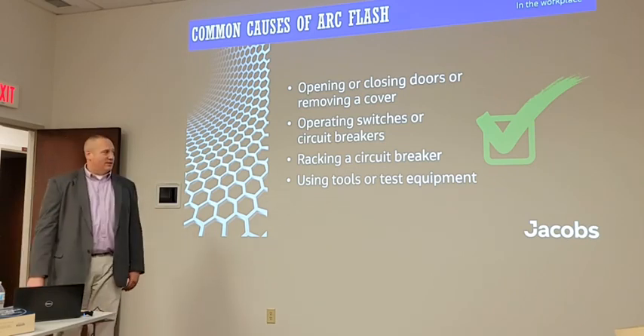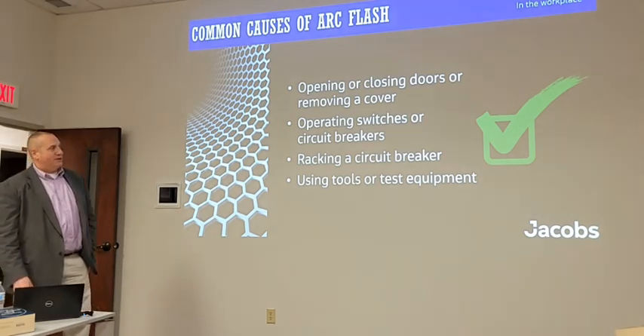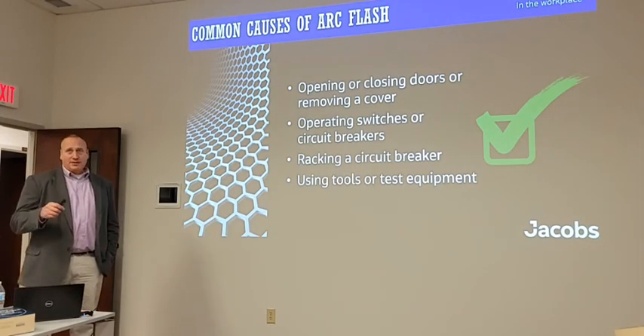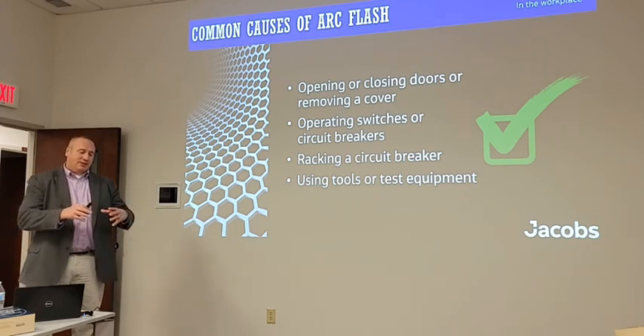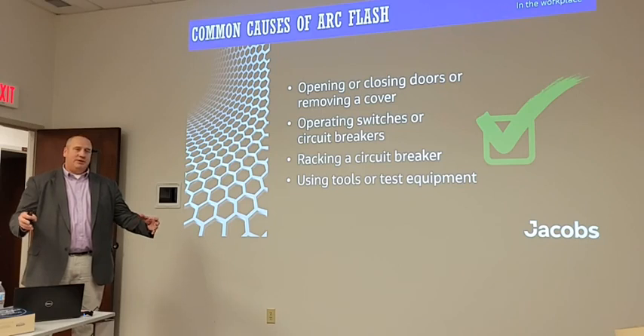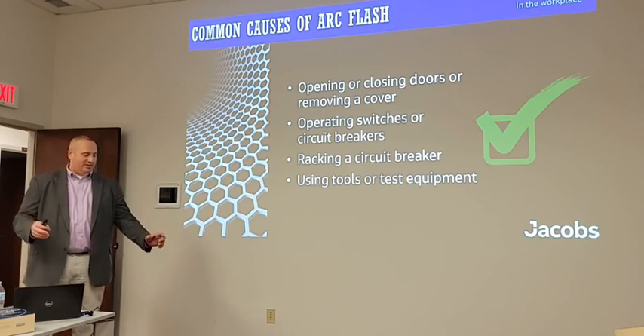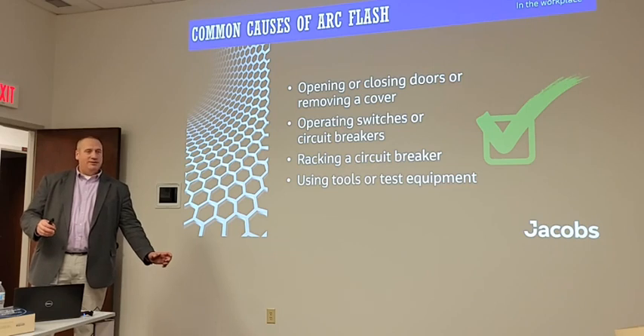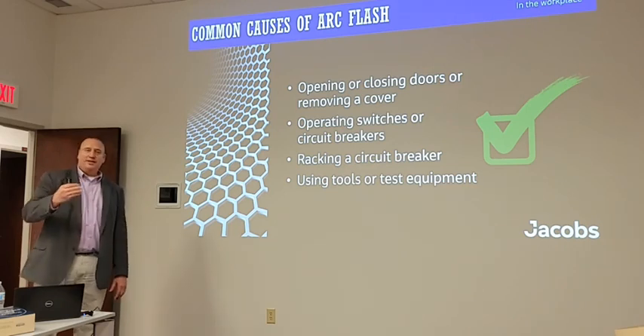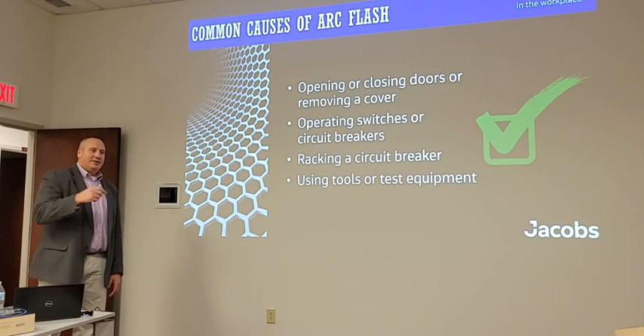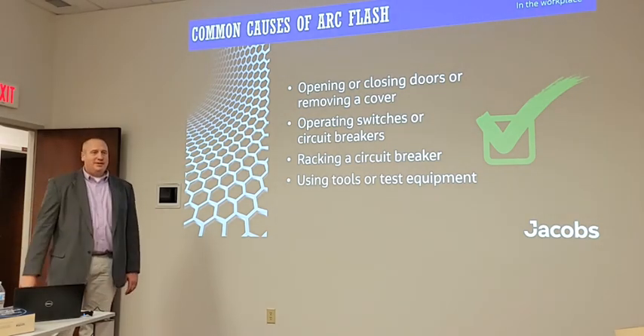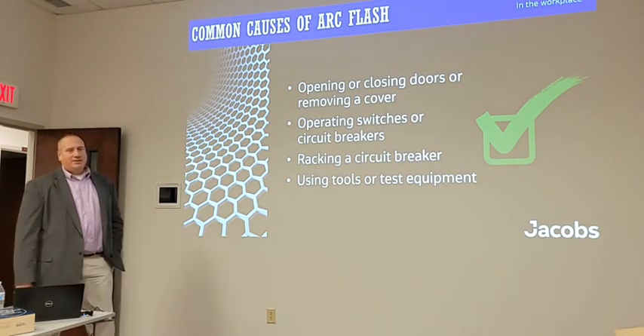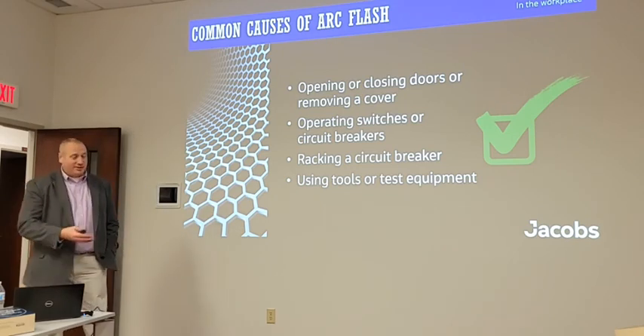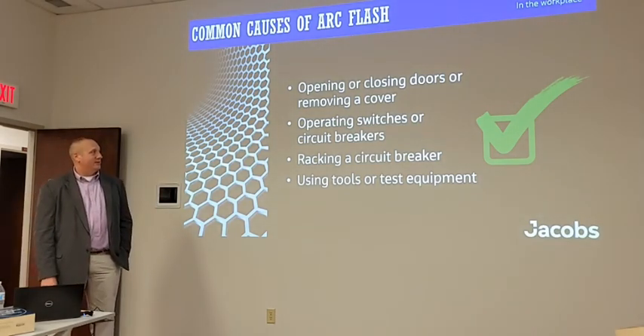I responded to a failure that was an outdoor, air-insulated medium voltage switch, where you could see the charring on the concrete floor of the switch, where there's an arc flash vent inside the switch, and you see this little outline of a mouse in the corner over here, and then the remains of the snake that was following it. The mouse was able to jump, and when the snake got up there and crossed phase to phase, it initiated the arc. The snake blew the gear up. So you never know what's going to be going on inside there when you open and close the cover.